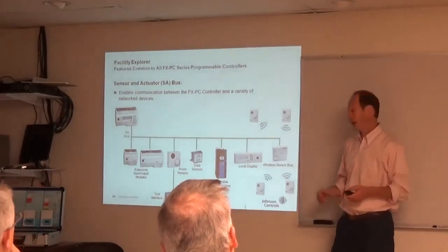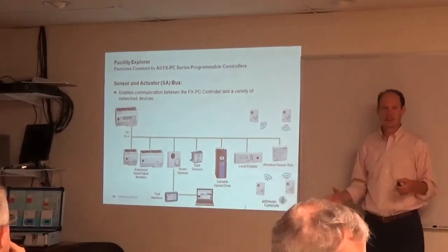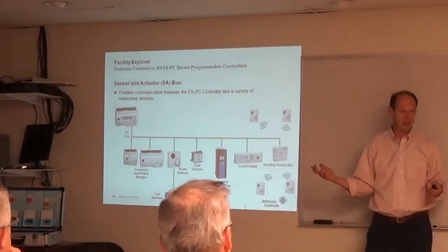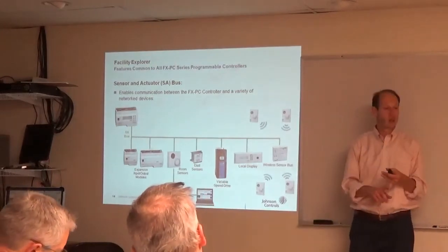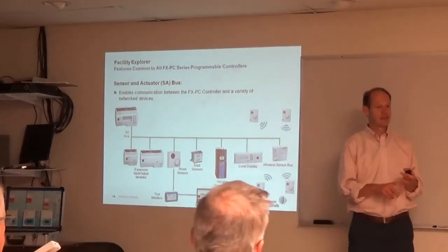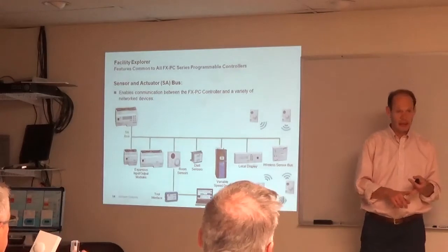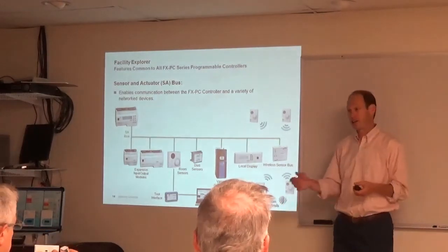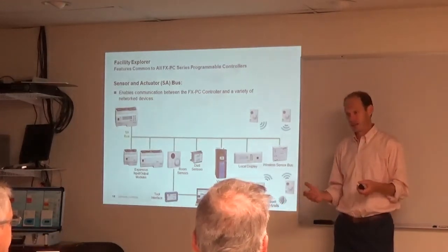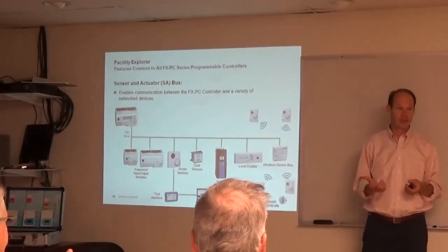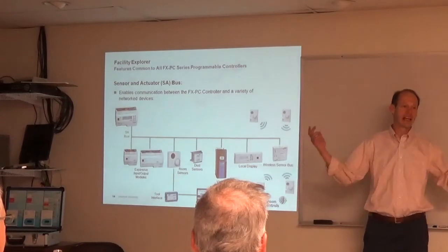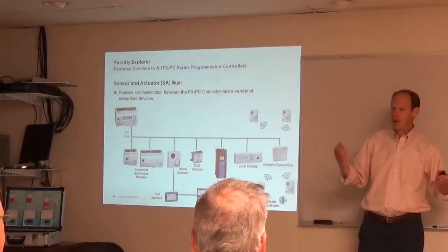It works very well, and I did a job with 1,300 VAV boxes all wireless in Chicago. It worked awesome. It was great because they didn't have to use any wire for the sensor bus. They didn't have to use any wire for the communication bus. And in Chicago, it all has to be in conduit. So there's a big labor savings and time savings and cost savings. The hard part is that you've got to get your electrical to agree to it, right? The electrical's going, well, you're taking away all my work. Okay. But you're not, actually.